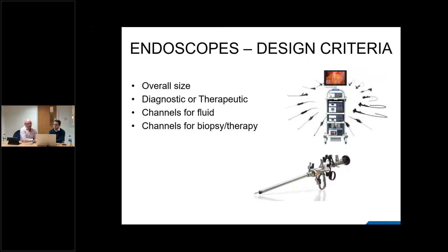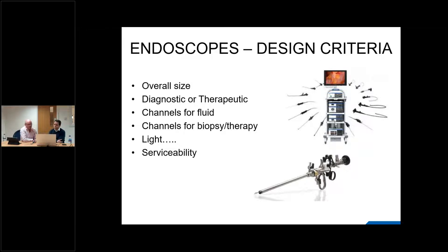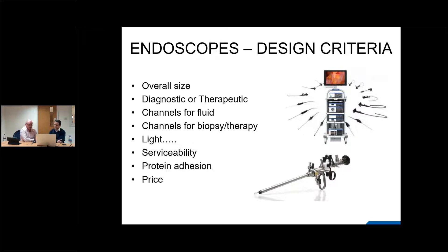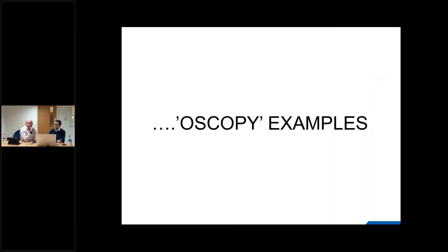The whole thing is a compromise between what you want to do: channels for fluid, biopsy, and therapy all reduce the area available for optics. You also need serviceability — the easier and cheaper the instrument is to repair, the better. And cleanability is critical. Some miniaturization technology is remarkable but isn't cleanable, making it single-patient-use. If the cost per procedure is £50,000–60,000, it's just not going to happen in the modern environment.